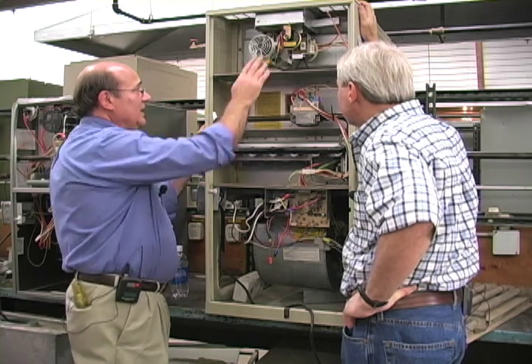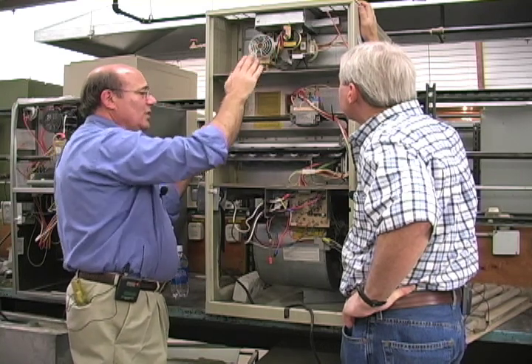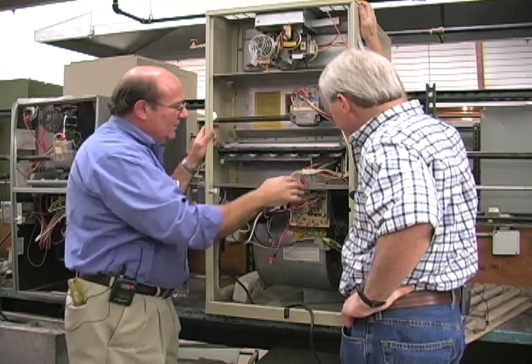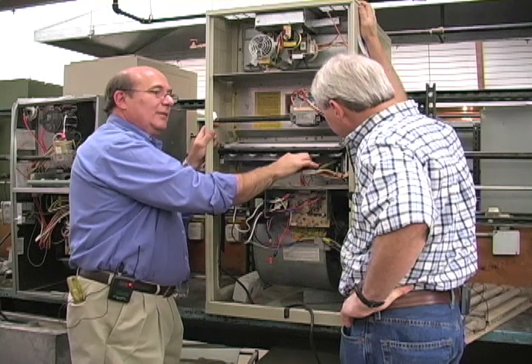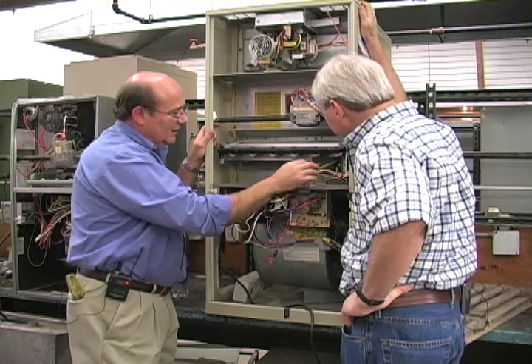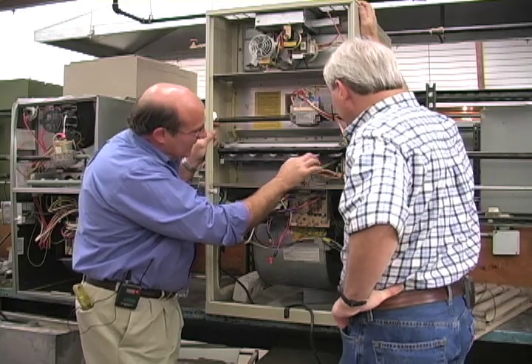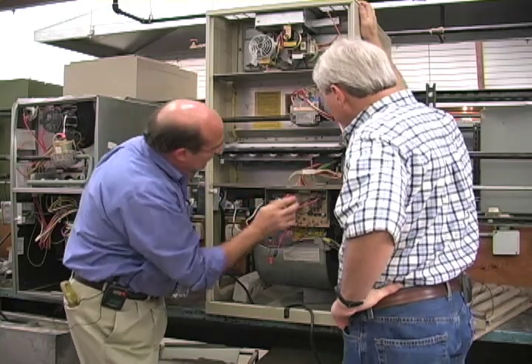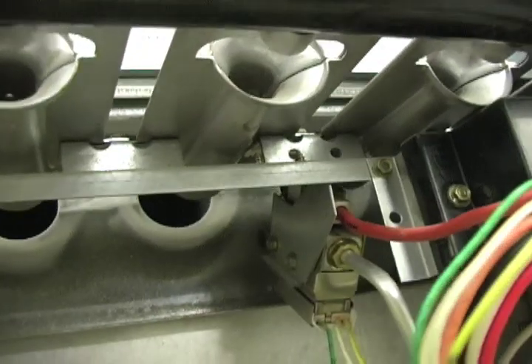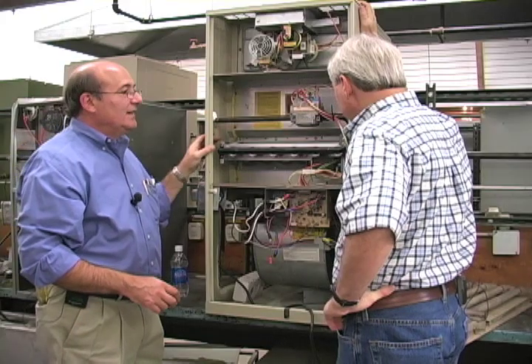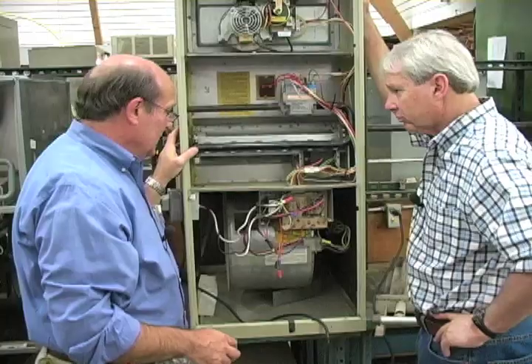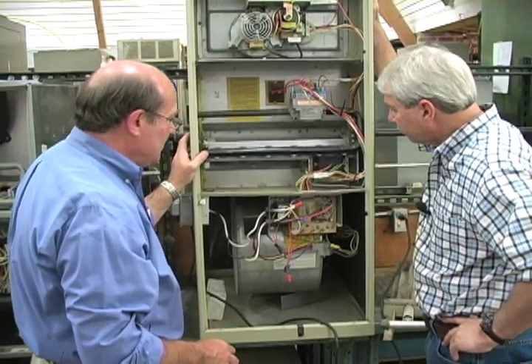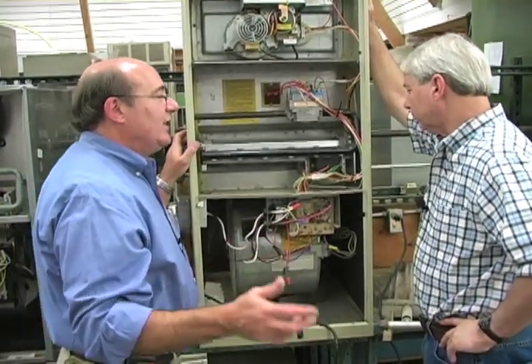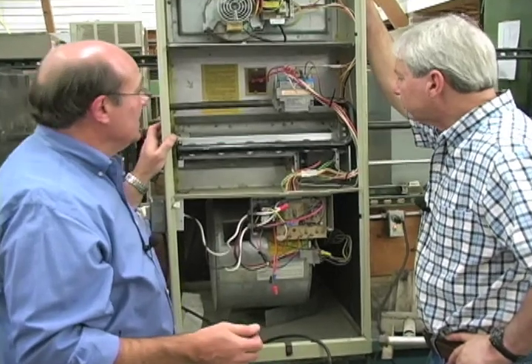But that's the primary difference, is the combustion blower motor, and secondarily is the fact that we've got an intermittent pilot. We don't use a standing pilot light any longer. This is an electronic igniter over here, and you can't quite see it in this, and in fact this furnace isn't gas piped, so I suspect that there's a defect in the furnace itself and the school hasn't piped it in place, but we can at least show you how the sequence of operation works on it.